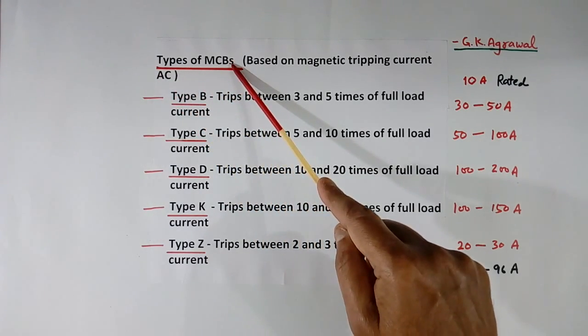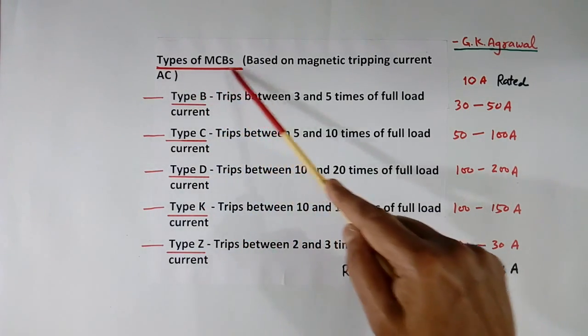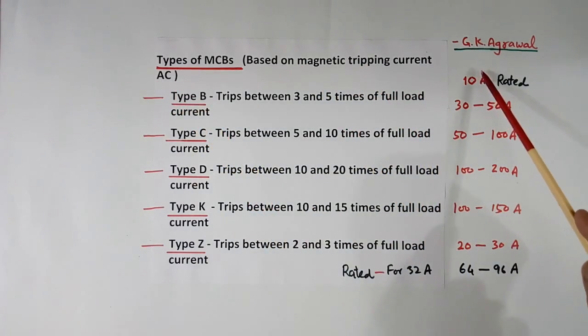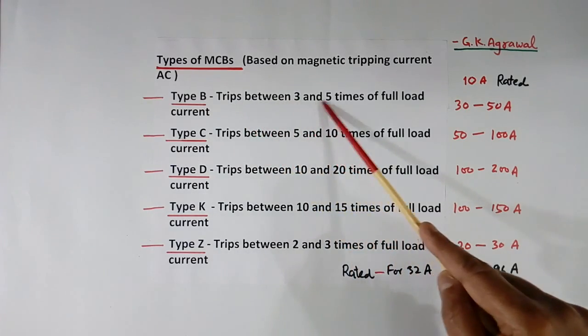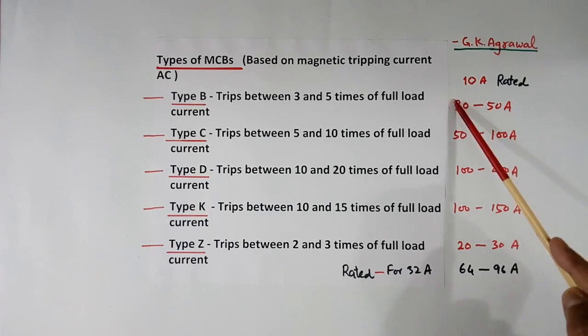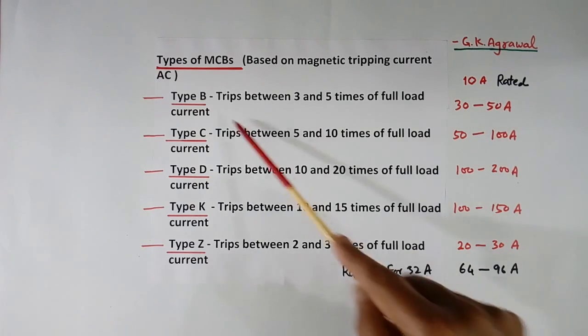Now types of MCB. There are 5 types: B, C, D, K, Z. They are defined based on magnetic tripping current, AC current. Suppose we have MCB which is rated for 10 A, or we can say full load current is 10 A. This is just an example. Then type B MCB will trip between 3 and 5 times of full load current. 3 times of this current means 30 A, 5 times means 50 A. So MCB rated for 10 A will trip between 30 to 50 A, provided it is type B.